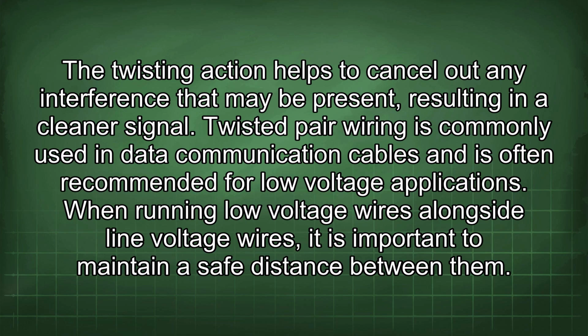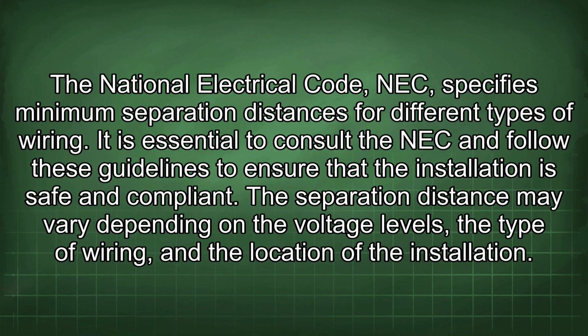When running low voltage wires alongside line voltage wires, it is important to maintain a safe distance between them. The National Electrical Code (NEC) specifies minimum separation distances for different types of wiring.